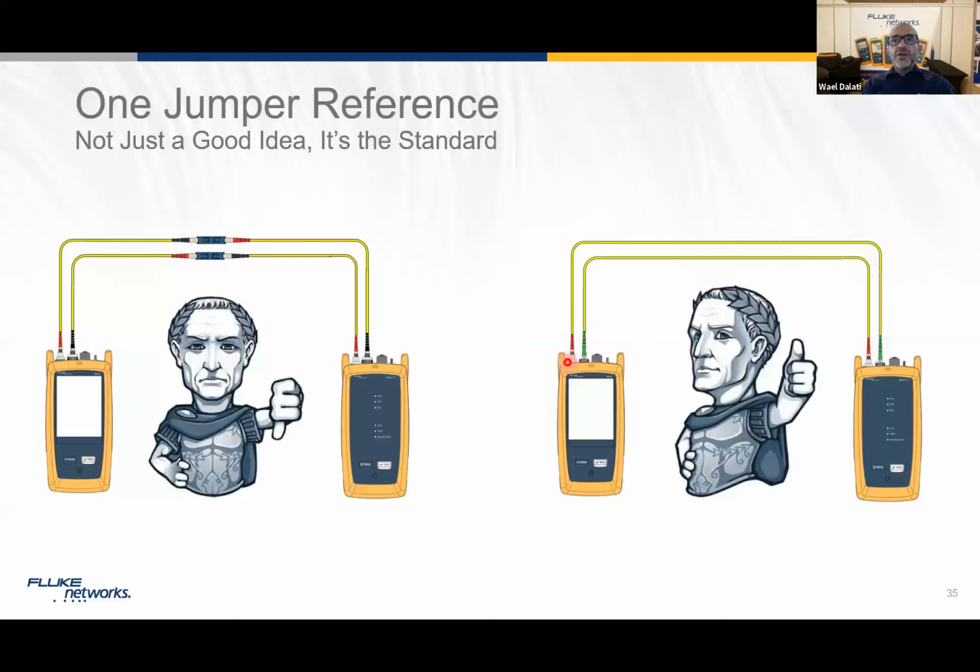So that's why the correct methodology of doing a referencing is to do it at least once a day, or multiple times a day if I am going to keep my tester away from testing for a couple of hours and I probably need to disconnect my tester. So how to set the reference?